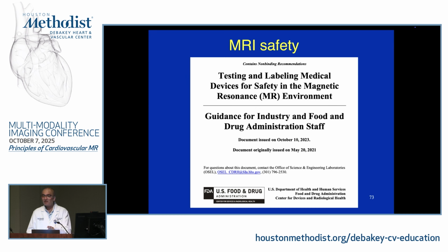But we can't do that without knowing, right? And if you look at it, the concern with implanted devices, the reason why for a long time we didn't scan people with pacemakers and defibrillators. If you look in the literature in the 90s, there were cases of deaths. People that had a pacemaker and went in and got an MRI scan and died, right?